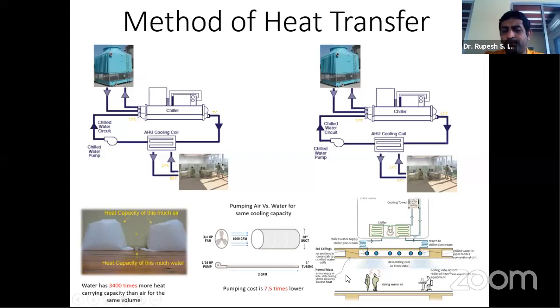So radiant cooling could be a process where we allow water to flow into the slabs, or into the panels which are attached to the false ceilings, or in the false ceilings itself, or in the walls itself. That could take out the heat in a much more effective way, which is 3,400 times better and faster than using air. So on the plant side, how would that affect?